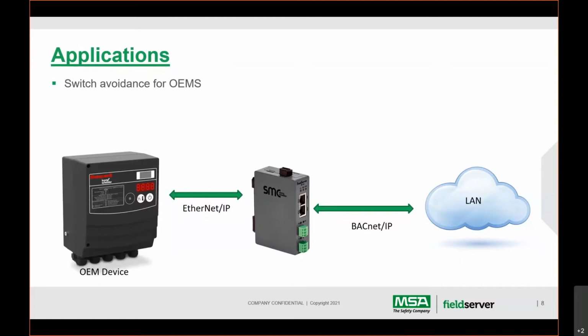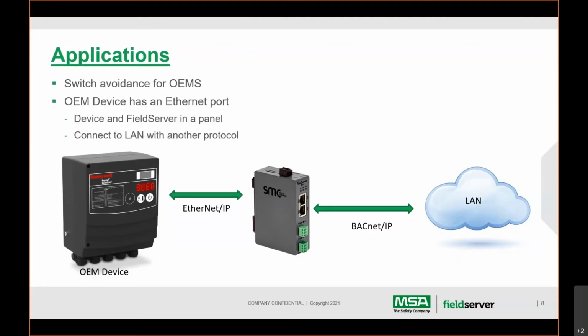But now you want it to go into a BACnet IP network and you need a field server bridge. So with one Ethernet port, you'd have to put a switch in there. You plug the Honeywell controller into the switch, the field server bridge into the switch, and then you plug the local BACnet IP network into the switch as well. And that gets a little costly, you're losing panel space. Now with the two Ethernet port, you don't need a switch within the boiler panel itself. You just plug the controller into Ethernet one, the LAN port, and on the second port, you plug it into the BMS network. That solves it pretty quickly.